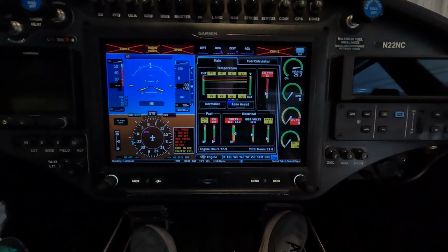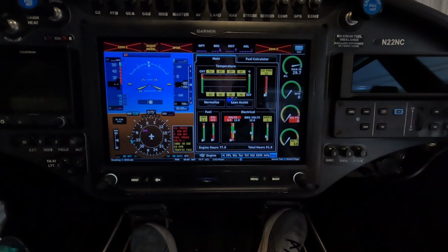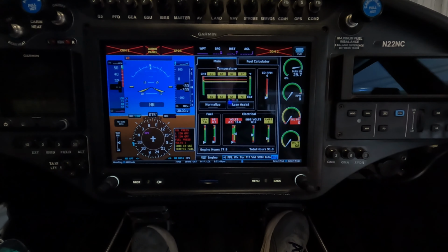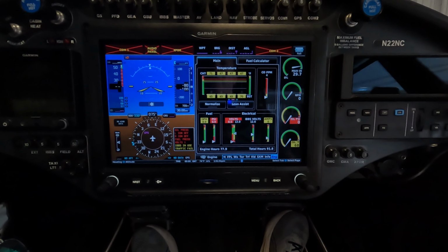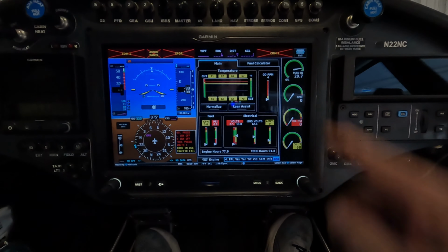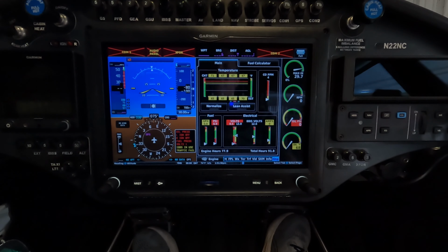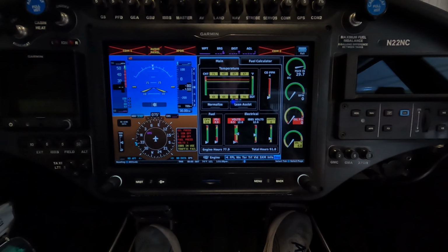So now it should come down to 0. It did its 12-second self-test. Let's see what it goes down to, where will it stabilize? So it's now showing 4 parts per million, which is incorrect. It should be 0 if calibrated.